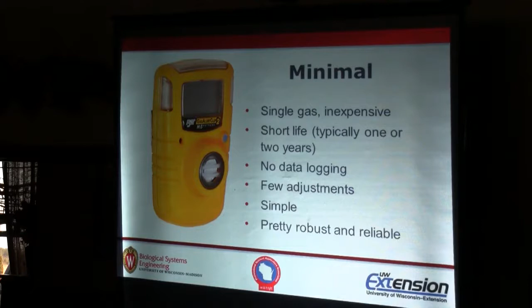I'm going to disagree with you a little bit on pumped instruments versus diffusion or non-pumped instruments. The pump on a gas detector is made to simulate diffusion conditions, but what it does is just draw atmosphere at a distance into the diffusion sensor, into the diffusion chamber. So if you had a vessel and put a diffusion instrument and a pumped instrument in it at the same time, filled with gas, they're going to read the same thing at the same time. You won't get any difference, because the pumped instrument is made to simulate the instrument being in diffusion mode - if you overpressurize it, the sensors won't work right.